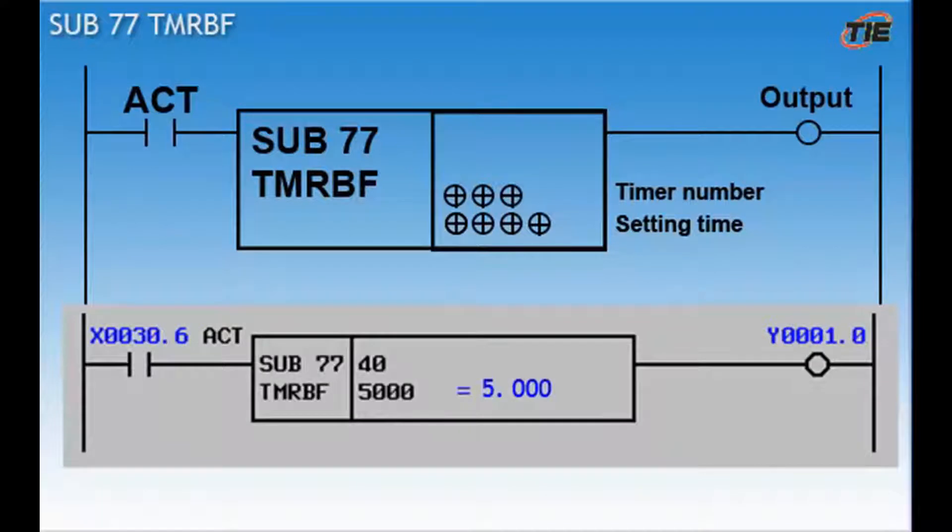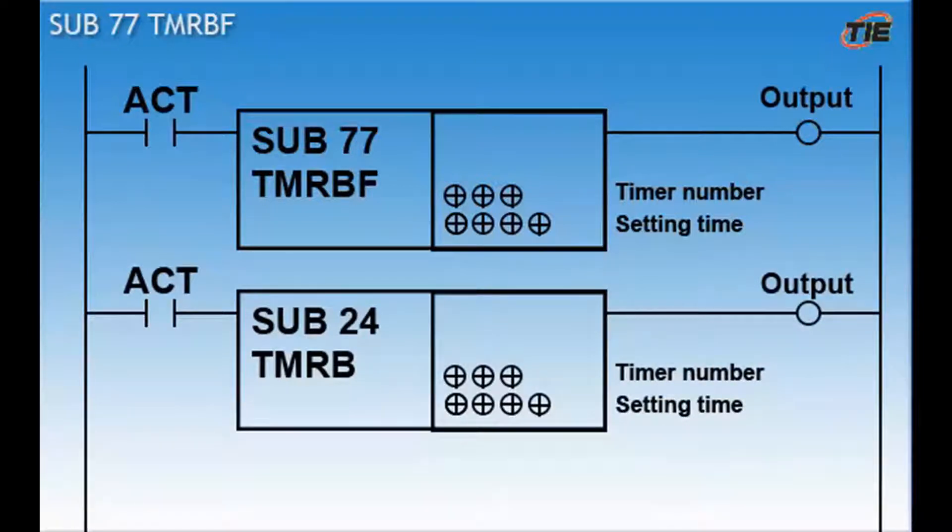The next timer I'm going to talk about is the sub 77 fixed off delay timer. This is called a TMRBF timer. It works a little bit different than the other timers. In this case, the output turns on as soon as the action command goes high. When the ACT command goes low, the output will stay on for the time shown here. Basically, this is an off delay timer. This is fairly new to the FANUC. Up until this time, all timers were on delay. TMRBF and TMRB timers share the same timer numbering system. Be sure to use a unique number for each. The time values can be set up to 546 minutes.